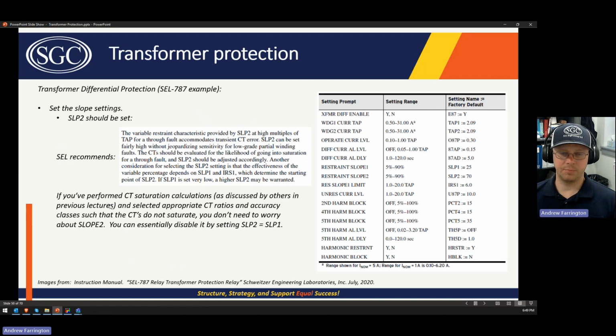If you've done your job, like if it's a new site and you've done your CT saturation calculations and you've sized the CT cables, the conductors, correctly such that you don't saturate your CTs for fault current, then slope 2 is kind of irrelevant. You can set it the same as slope 1 because your CTs aren't going to saturate, and so therefore it doesn't matter. But there may be an instance where you're replacing an existing electromechanical relay, and they don't want to run new cable because they don't have drawings for the old cables and they don't know where they are, and the conduit's buried and there's no knowledge of it.